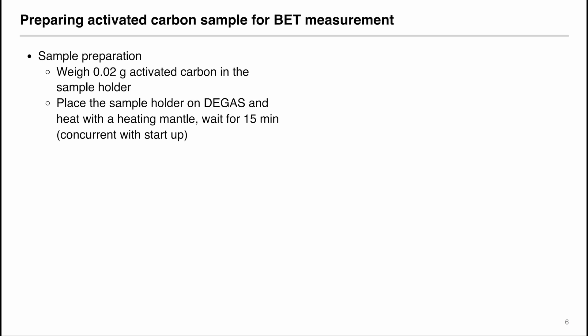When preparing the sample, weigh 0.02 grams of activated carbon in the sample holder. Then place the sample holder on the degas position, and heat the sample holder with the heating mantle. Then wait for 15 minutes. This can be done at the same time when the instrument is starting up.